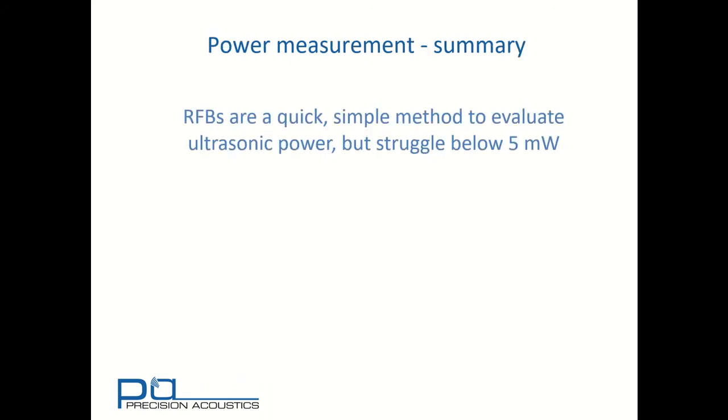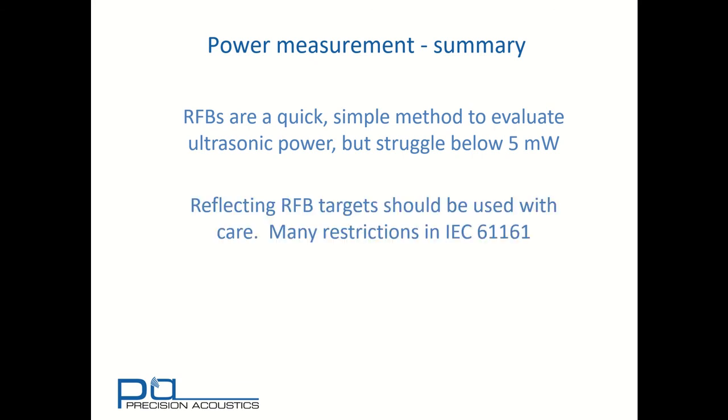In summary, we've seen that radiation force balances are a quick, simple method to evaluate ultrasonic power, and struggle when powers are below 5 milliwatts. Reflecting radiation force balance targets should be used with care, and there are a number of restrictions on their usage listed in IEC 61161. Hydrophone scanning can measure very much lower powers, but is a much slower operation with much higher uncertainty. We hope you found this interesting. If you did, come back and find some more of the Precision Acoustics tutorial videos.